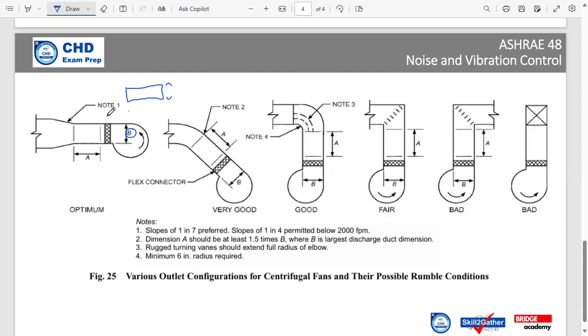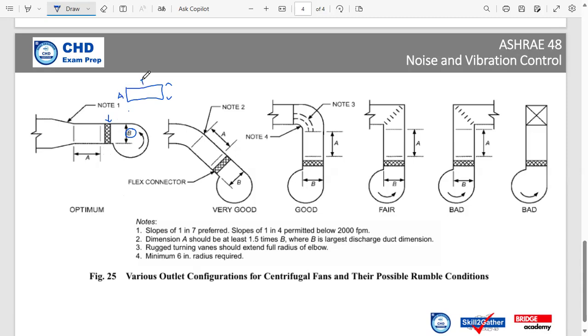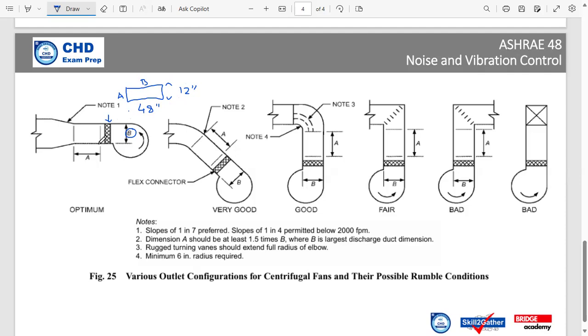Now what ASHRAE actually says is after the centrifugal fan, you must have a flexible joint. It may be cloth or it may be fiber. And after that, we must carry on duct similar to the size of the opening of the centrifugal fan. Let's say the centrifugal fan opening here at this point is A by B. Let's take a numerical value - so let's say this is 48 inches and this one is 12 inches.